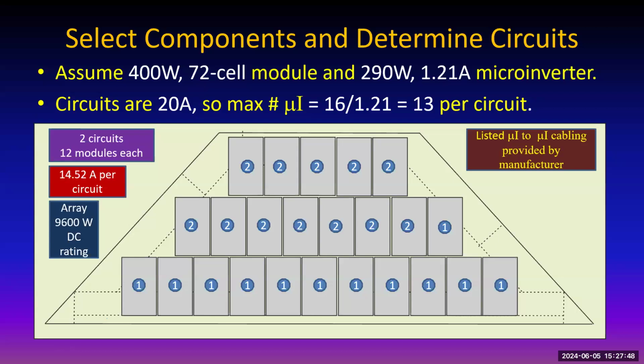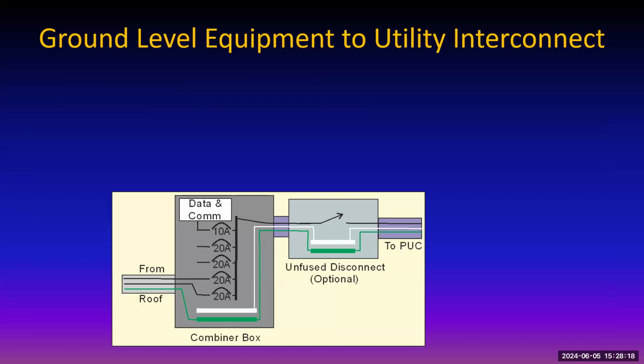The microinverter has cabling provided by the manufacturer. Circuits are fed to a combiner box at the ground level by way of conduit, because there's a junction box on the roof where the open wiring is converted to wiring in a conduit. And that's that. So once you get down to the ground, you're going to have something like this, a combiner box with circuits coming down from the roof. And these 20 amp breakers, by the way, are 2-pole 20 amp. We've got a single line diagram here.